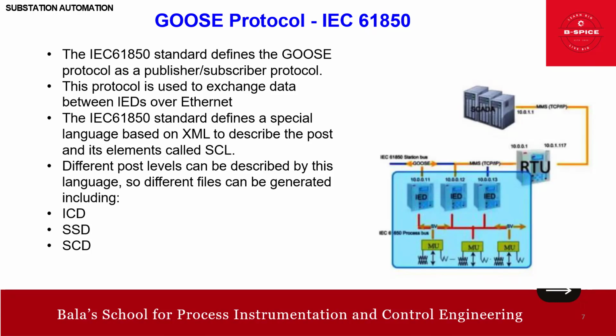The SCD file includes configuration of GOOSE messages, defining which IED publishes and subscribes to specific GOOSE datasets. This ensures that GOOSE messages are correctly routed and interpreted by all devices in the substation. So this covers some concepts about GOOSE and the ICD, SSD, and SCD files. Just remember, in instrumentation we have the DD file, device description, and CFF in Foundation Fieldbus - something similar to that, friends. That's it, this is about GOOSE.